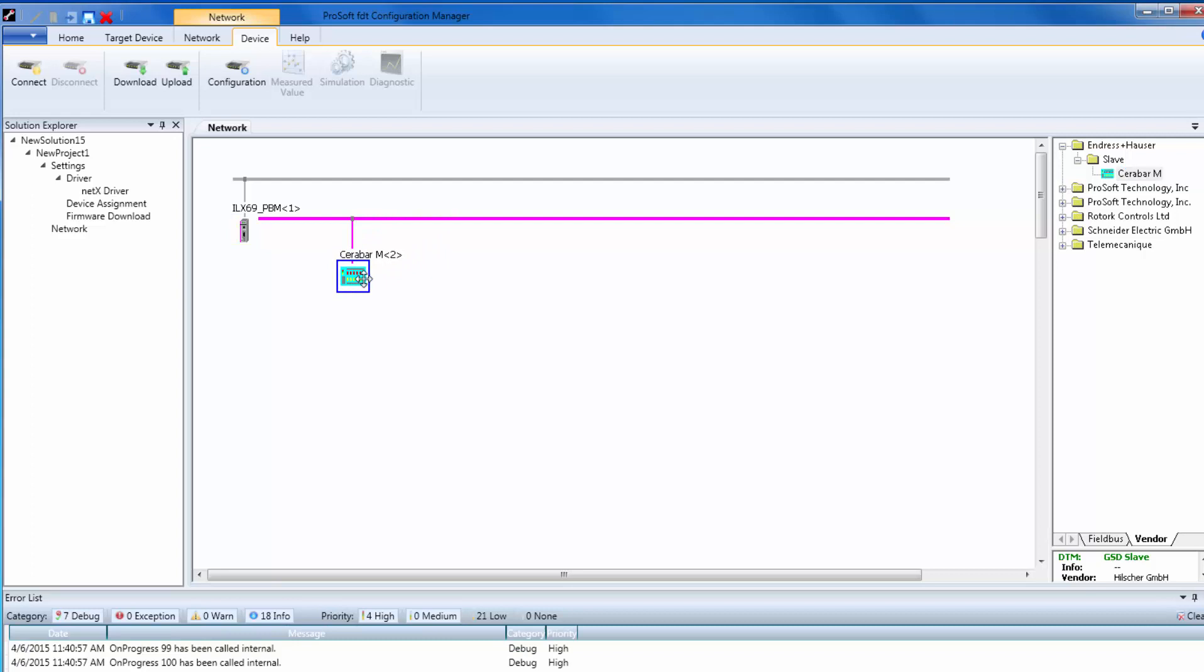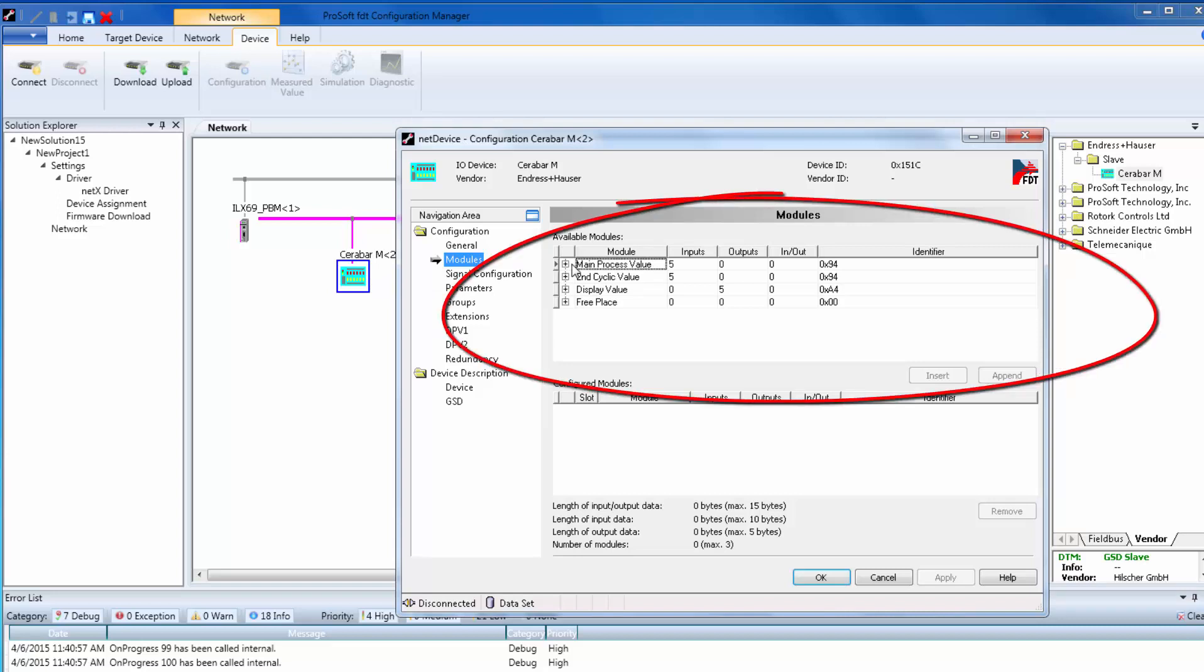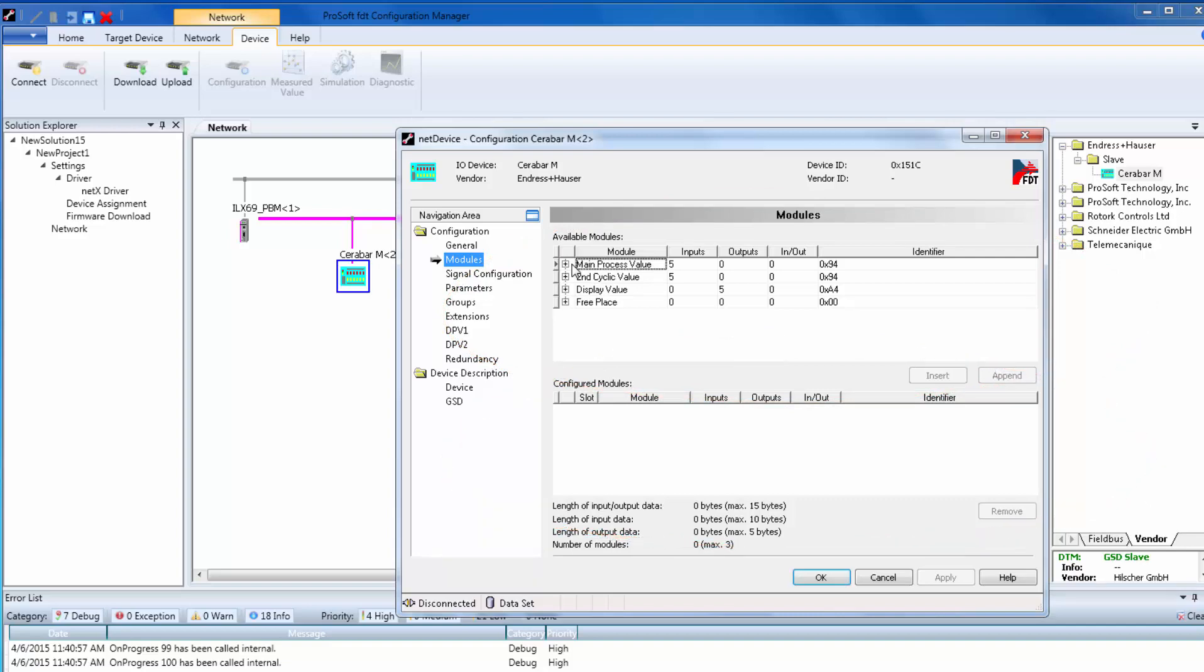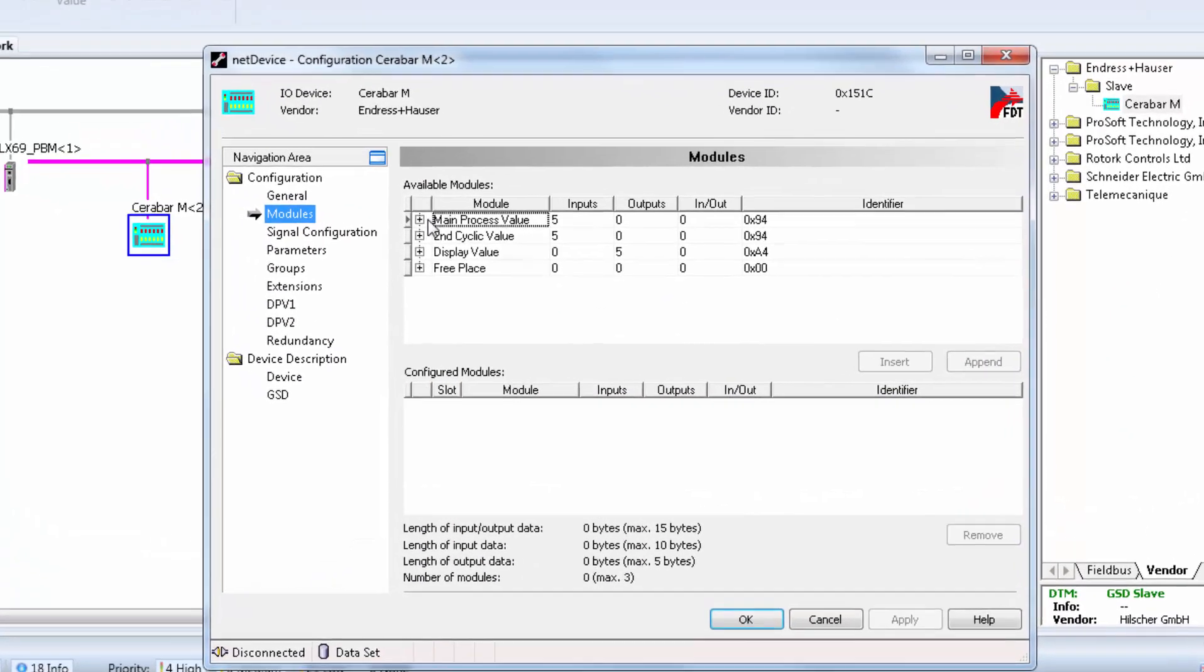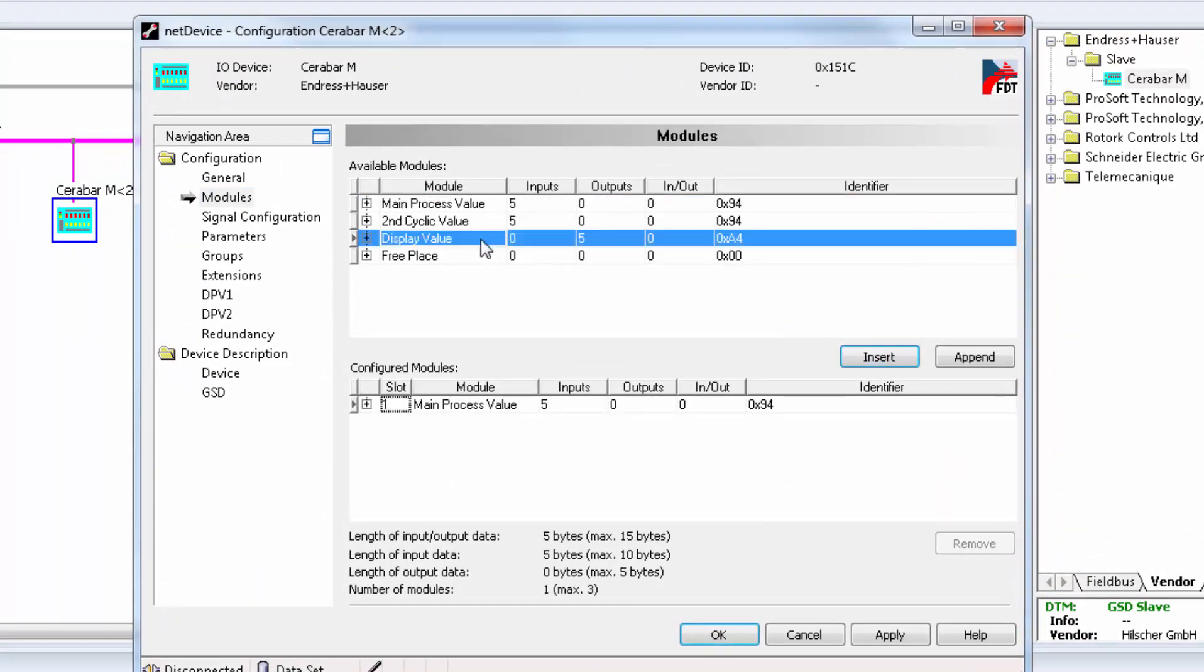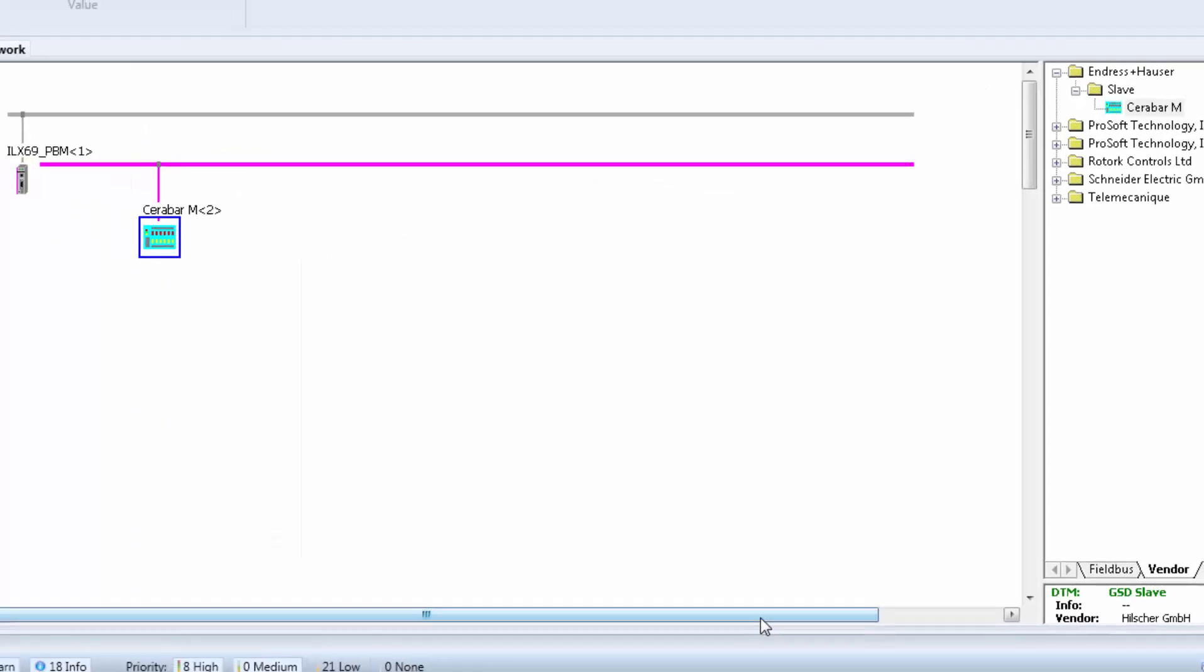Once the slave is dragged onto the network line, we can then add modules to designate how much data we want to exchange between the master and the slave. You do this by double-clicking on the slave. The configuration is broken up into two parts. The available modules on top, and the configured modules on bottom. Just highlight modules from the available or top section, and then click on Insert to get them into the configured or bottom section. For my configuration, I am reading the main process value from my meter and writing the display value to the meter, so I will locate those and insert them into the configured section. And then click OK.